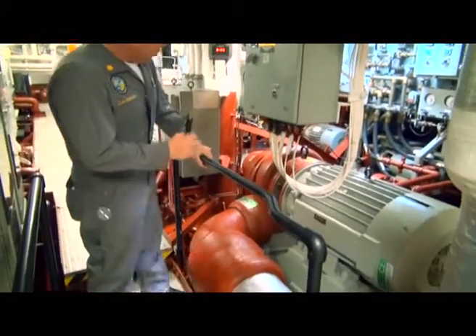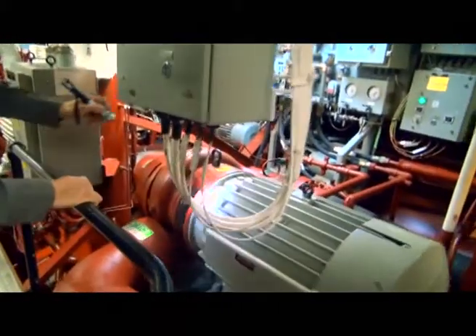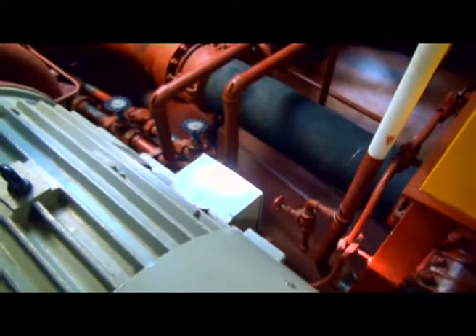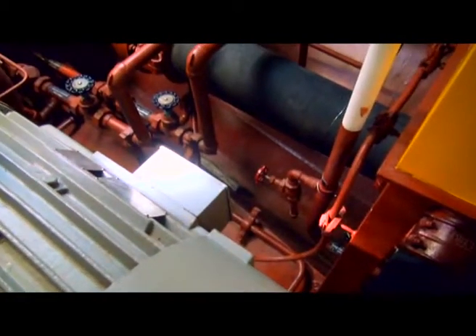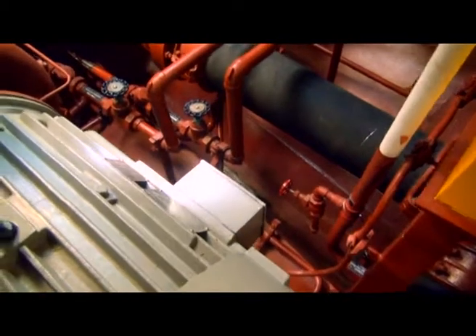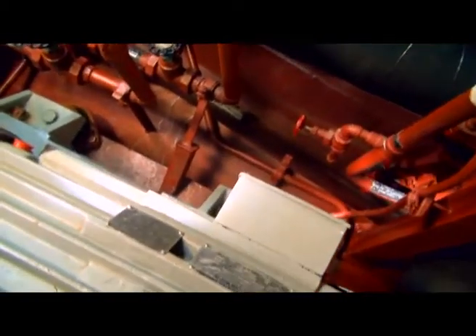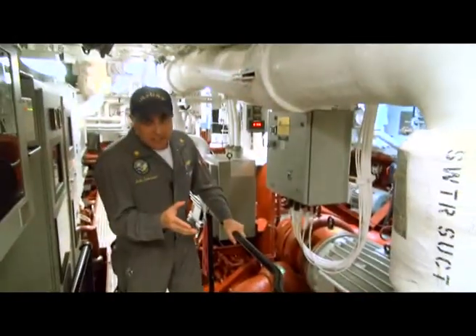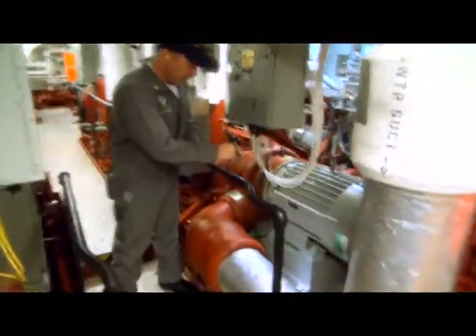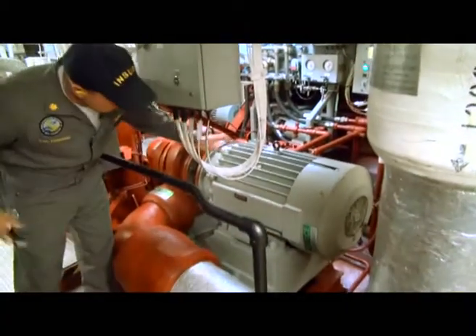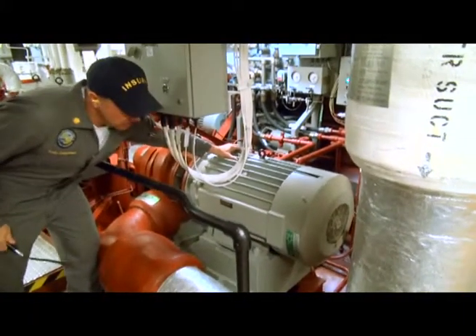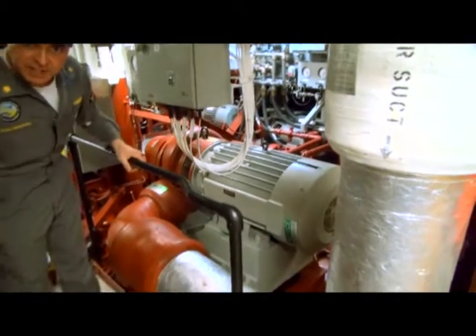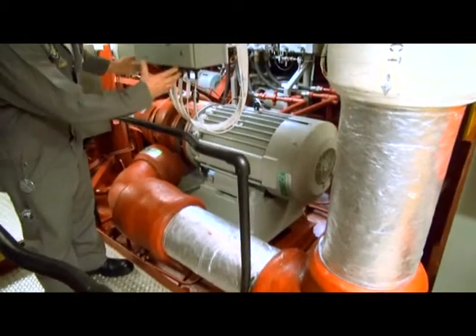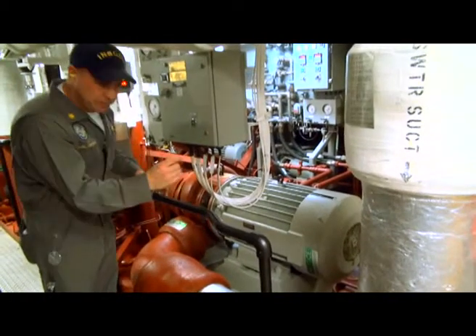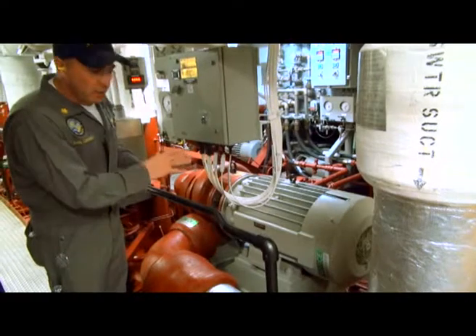The other thing, like the fire pump, is we're also going to check the motor terminal junction box. It's over here in this case. We check the box itself, make sure it's tight, and check that the electrical lead is intact, secure, and there are no electrical safety hits. When I'm checking the resilient mounts, this thing's on a foundation and it's got resilient mounts. I like to give the pump a grab and actually move the pump. That checks two things. It checks the mounts themselves, and it checks for any shock hits, any metal-to-metal contact, or any spacing issues that we have. So we check all that with one simple check.